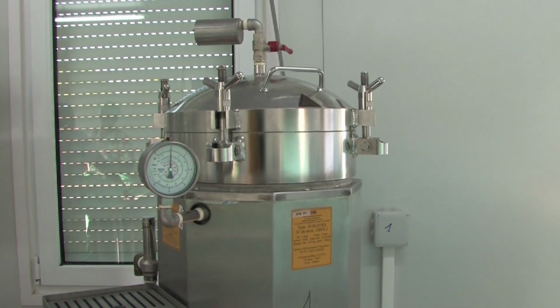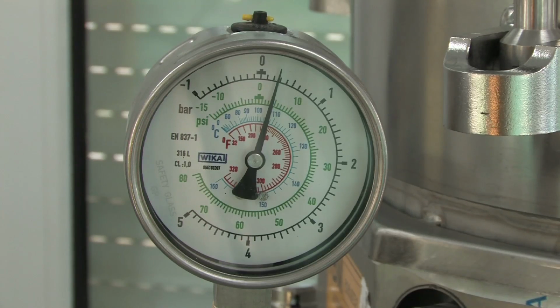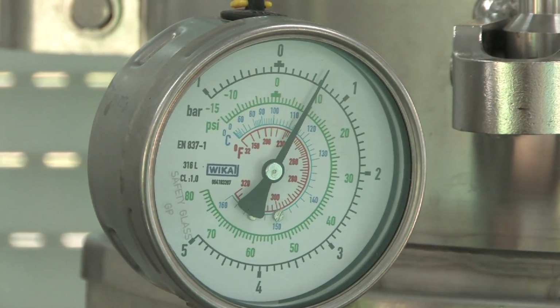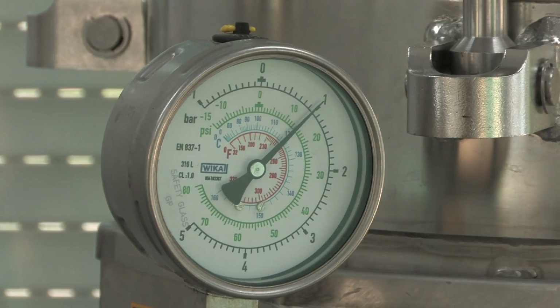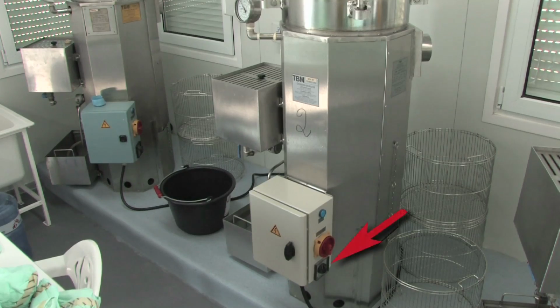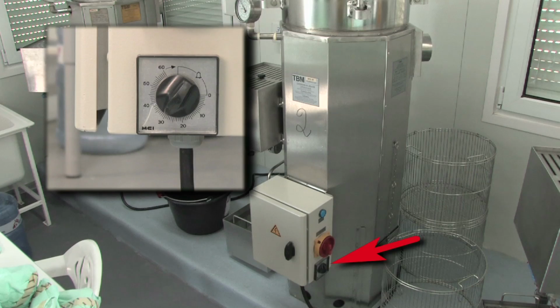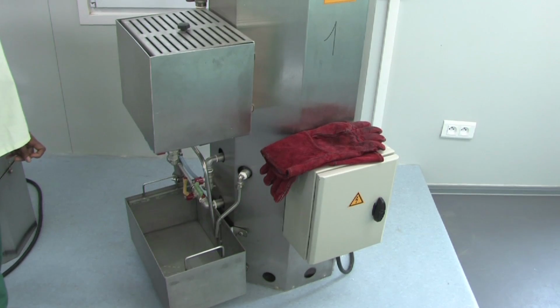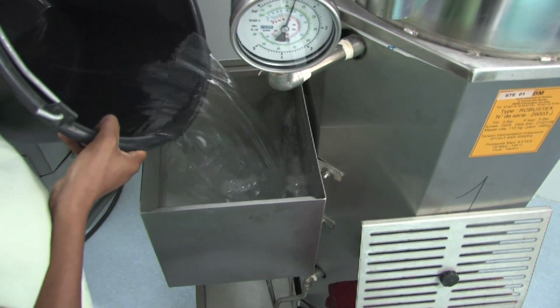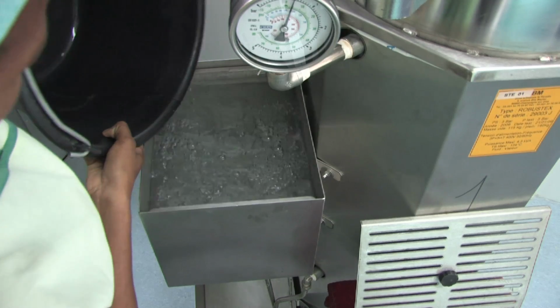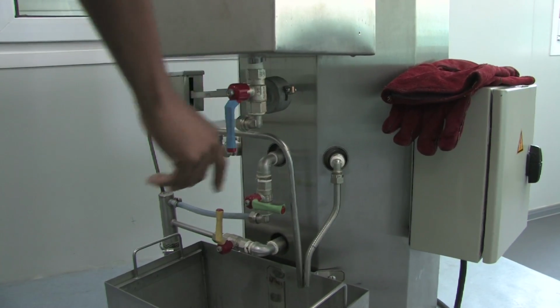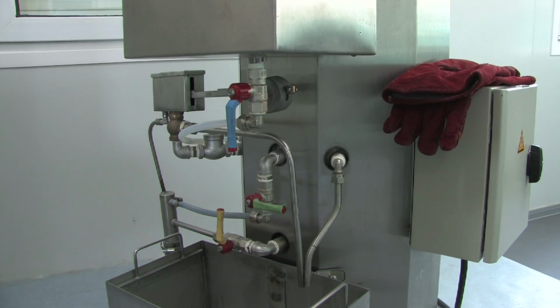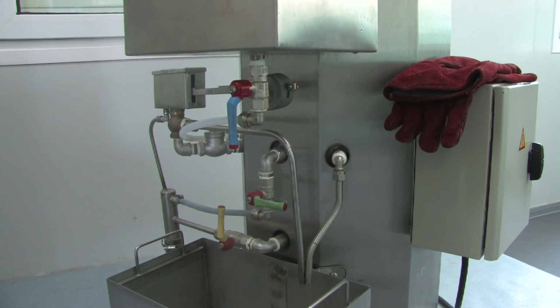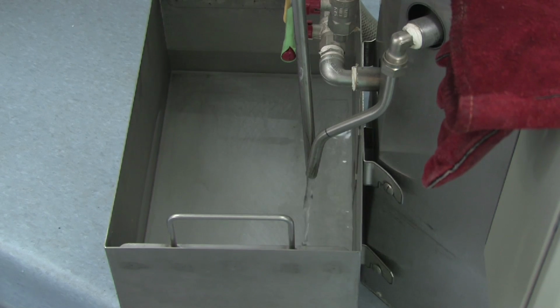The pressure gauge is used to monitor the pressure in the autoclave chamber throughout the entire cycle, and make sure it corresponds to the expected steam temperature. The timer, which is set to 10 or 30 minutes, signals the end of the sterilization plateau. 2 tanks are used for cooling the autoclave. The upper tank is filled with the coldest possible tap water. When the blue valve is opened, the water flows through the coil located in the bottom of the autoclave and empties into the lower tank.